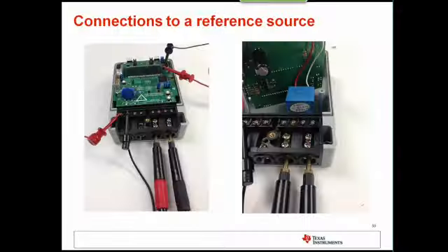And this is it connected to the one that we have in our laboratory. You can see the voltage inputs are connected separately from our high current input. This is 3-gauge wire, I believe, going into these things. We source 100 amps into these terminals, and you can tell they get warm. The thing will vibrate sometimes at these high currents, but it's designed for it, so don't worry too much about it.